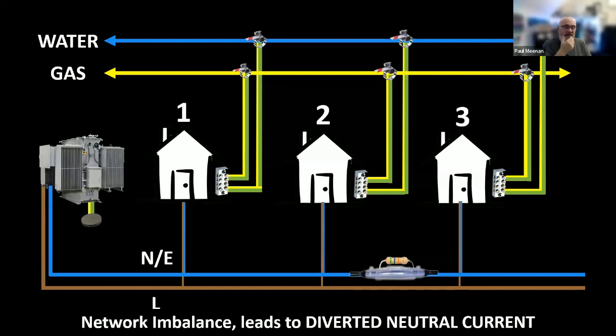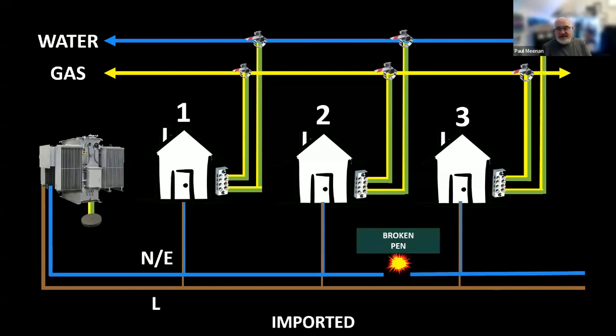So what we then find is that when you put a clamp meter on your earth wire, that water pipe, which is a lead pipe or an old copper pipe in the ground, some of the energy will divert into those lead and copper pipes, and it may travel all the way through and divert around the high resistance joint and into house number 2. So number 3 can be fed via the gas or water main into number 2. So that's known as diverted neutral current or neutral current diversion. And I've always said that when you've got energy that shouldn't be there on your earthing system, that's a precursor to a failed neutral in the supply network. So it's one of the things that we look out for, and we call it a broken PEN.